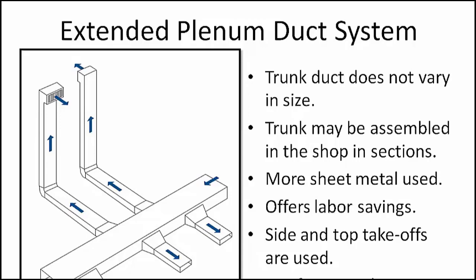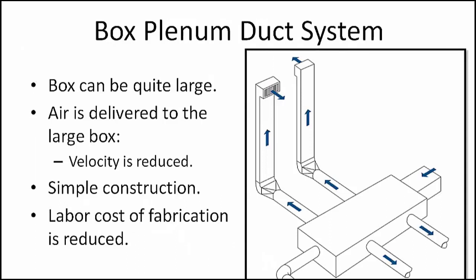The box plenum duct system, shown here, differs from the extended plenum in the size of the plenum. The box can be quite large — in some cases 3 feet wide and 10 inches deep — big enough to fill a hallway ceiling space. Air from the system blower or fan is delivered to this large box, where the air velocity is greatly reduced. From the box, the air is distributed through several individual branch ducts to the various rooms of the house. In cases where this system can be effectively installed, it has certain advantages over the trunk duct system: it is simple in construction, labor costs of fabrication are reduced, and it is very common with a flex duct branch system.